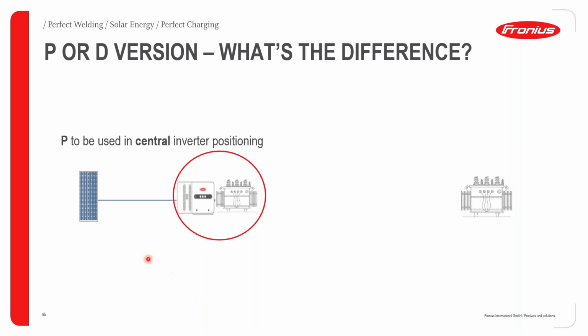So the pre-combined version means that from where you're connecting your PV system, you are coming with two big DC cables, plus and minus, and those are running a much longer distance from the PV installation than you'd have when you connect your inverter just next to the PV array. Therefore, if you look at this installation here, the AC connection cable from the inverter to the transformer, or the point of interconnection, or what we call the feeding point, is much shorter.